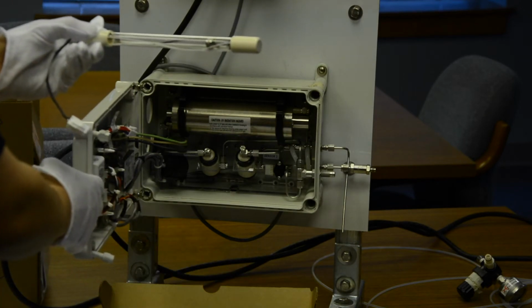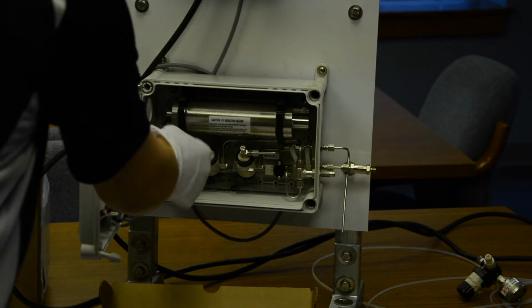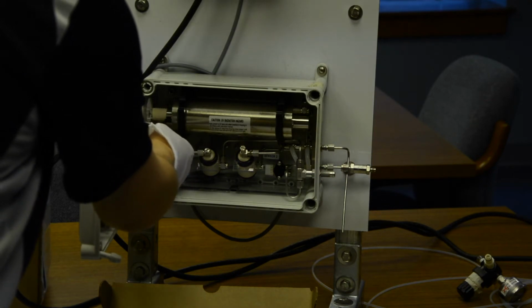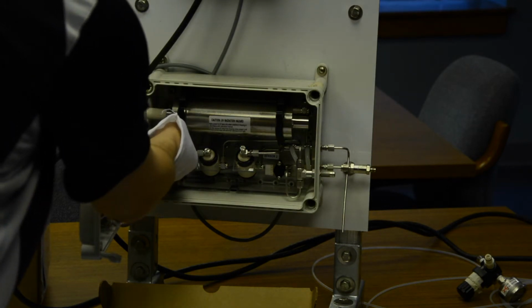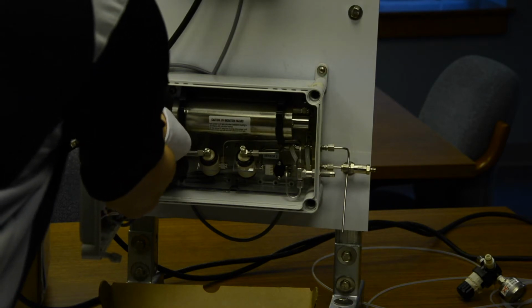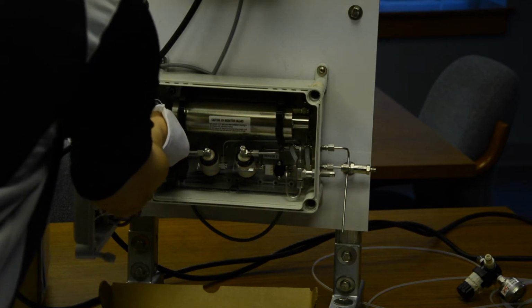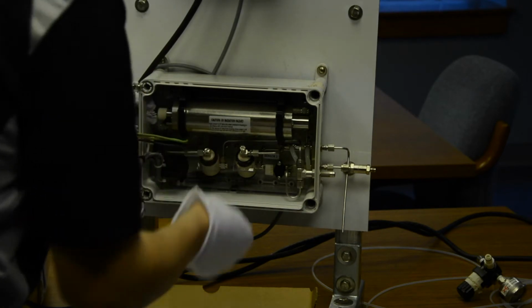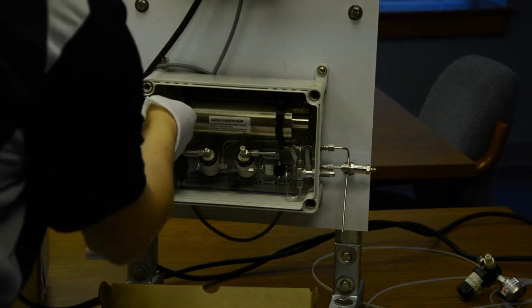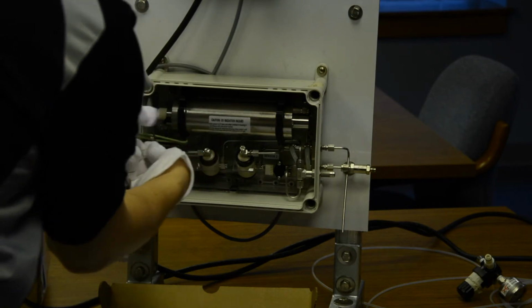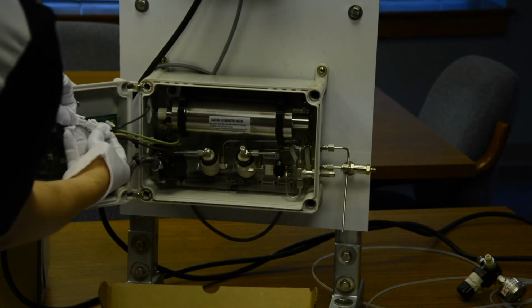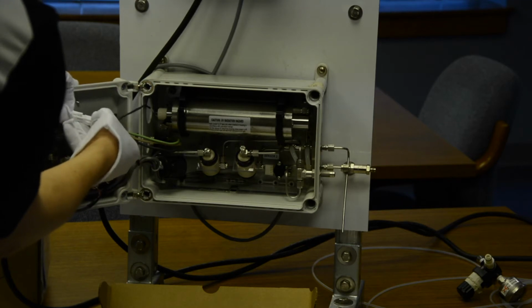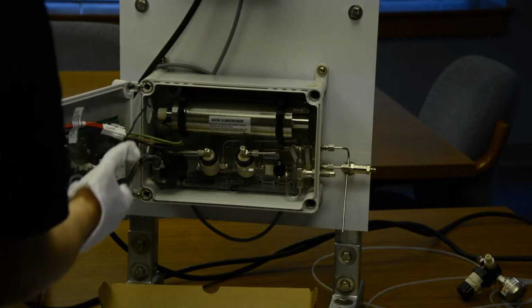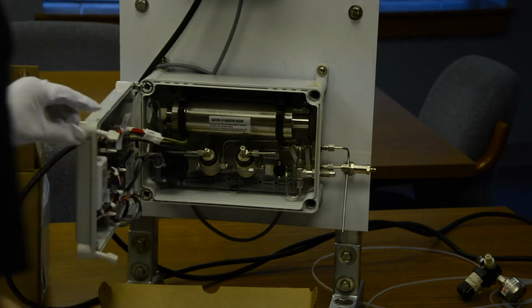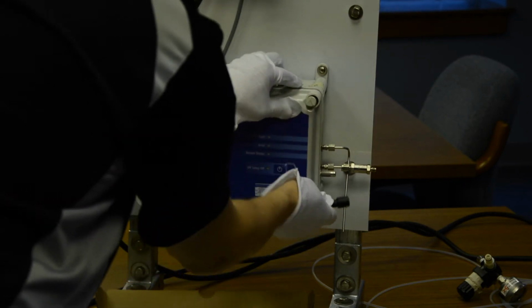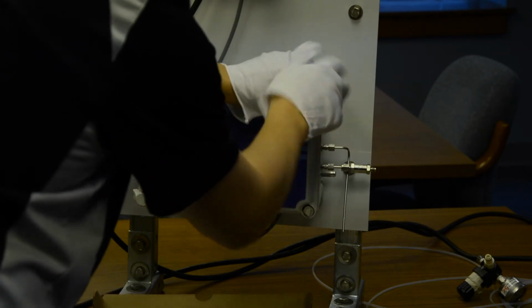And the installation is the reverse of removing it. Put it back in through the side, into the sleeve, and then tighten down, turning clockwise, the black retaining nut. After tightening it down in its sleeve, take the cord and thread it back through the access panel and reconnect it to the connector in the front of the panel. Now the UV lamp is installed in the kit. Close up the unit, 4000 or 5000 TOC unit.